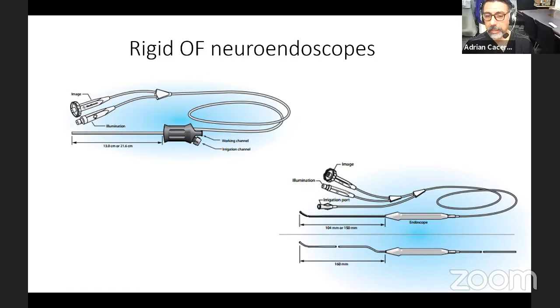So endoscope sheaths will enable you to put in a lot of instruments, and we have large working channels. You can see here, this is the MINOP invent system that was designed by Aesculap. This enables you through this oval channel to put dissectors and a number of scissors and different coagulation elements. This is below it, the other system, which is also very common, where you have various tubes.